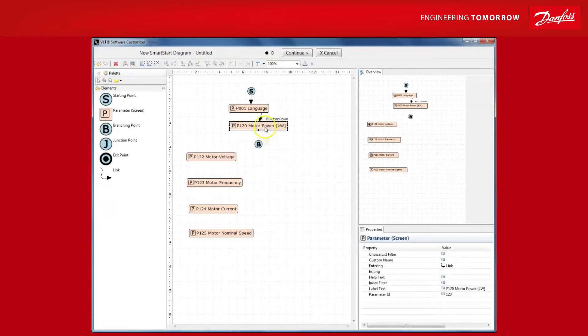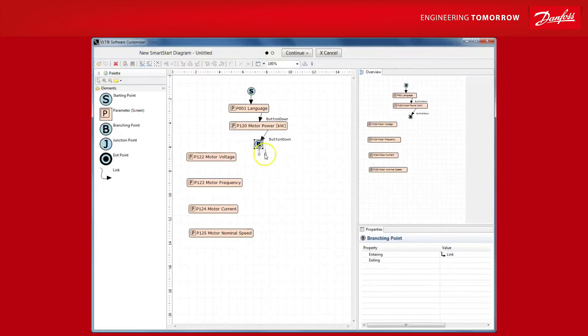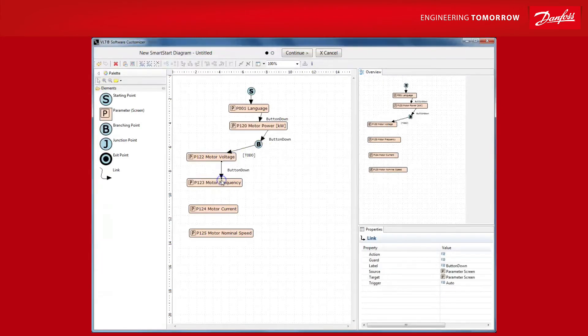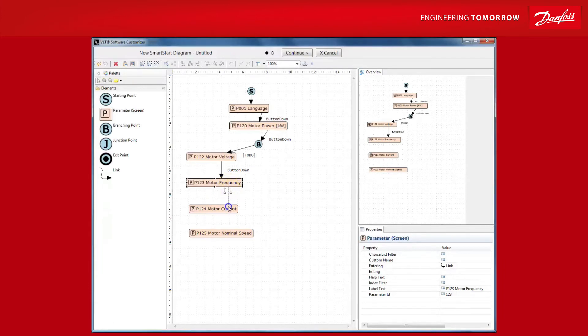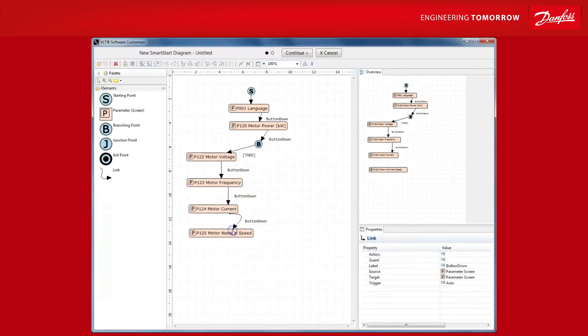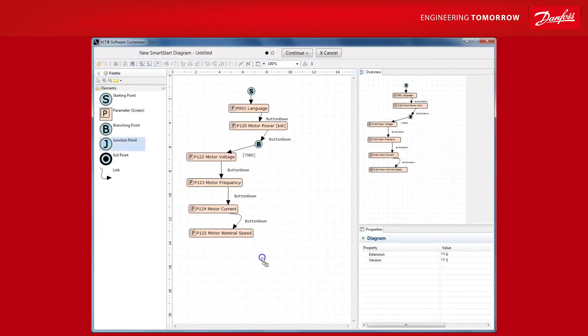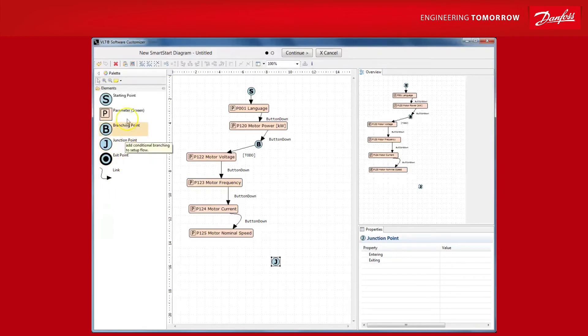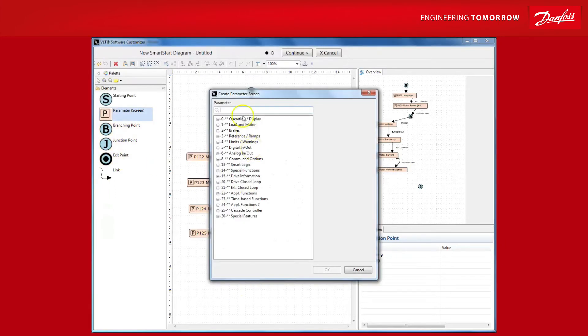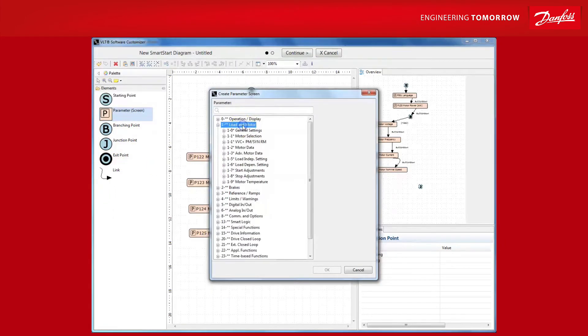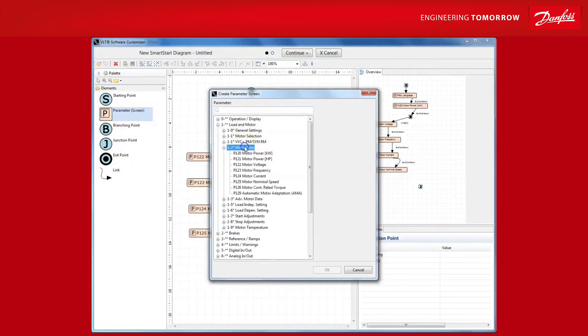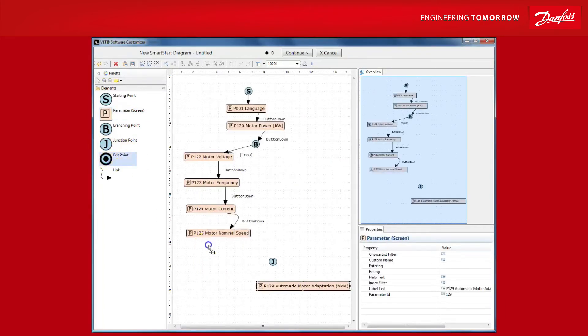Regardless of whether the user goes for our common 3kW motor or not, we always want to prompt to run an AMA, the automatic motor adaptation. This allows the VLT to have optimal control of the motor and thereby optimal efficiency of exactly the motor we have connected. To do this, you'll grab a junction element and link it up just like this. Add the AMA step and finally the exit point to end the wizard.